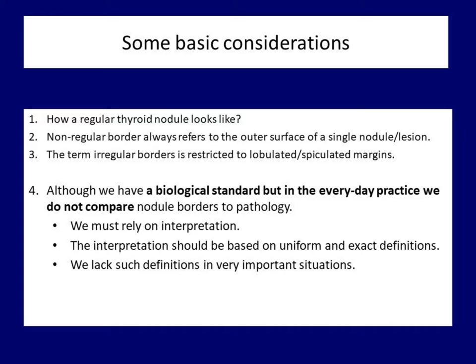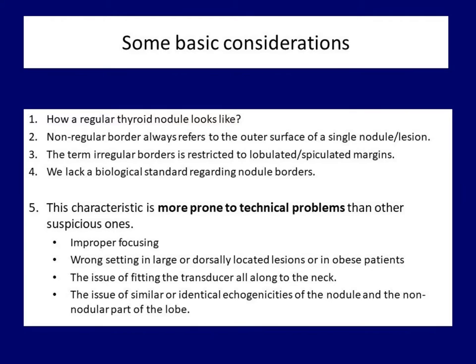The very basis of such consensus is the uniform and as exact as possible definition on which we can make a distinction between normal and pathological forms of borders. As we will see, none of the guidelines give such definitions. One of the reasons for the highest inter-observer variation of nodule margins among suspicious ultrasound findings is that this feature is very exposed to technical issues. Part of these problems can be avoided. Proper focusing and the change in settings from better resolution to better penetration are the clues. However, in obese patients or in large goiters, we cannot always prevent the technical problems.